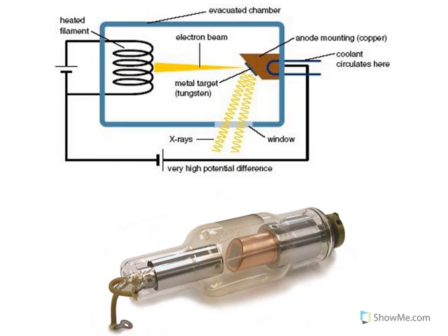It's a glass tube which has got a vacuum, and you can attach a potential difference to both sides. So you get electrons zooming off here and whacking into this bit here. You'll notice just there that the side of the glass tube's a little bit different. When these electrons whack against that, they give off the X-rays. The ones that come out of this bit here are the ones that are then used to take the X-rays. So you can see in the diagram above, that's what we would call the window.